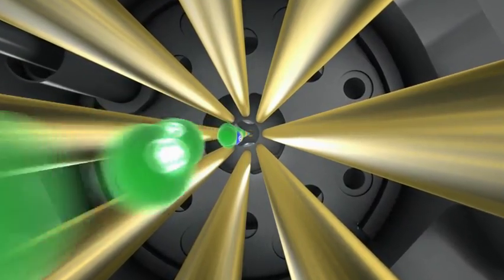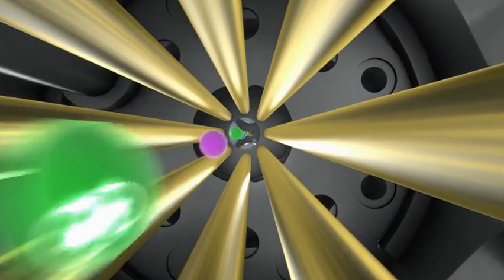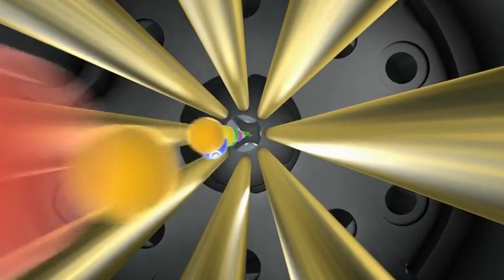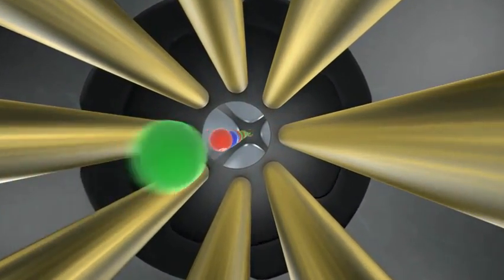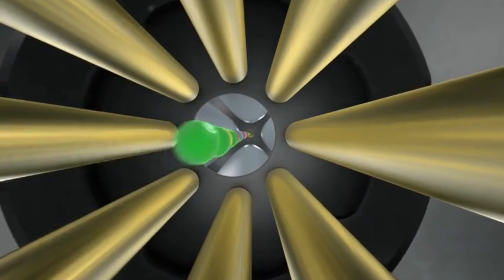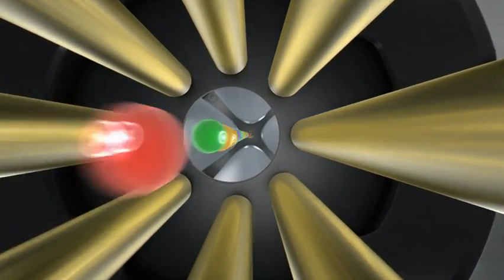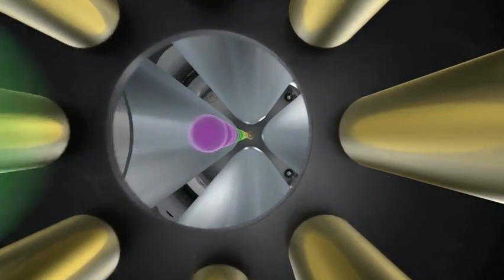Newly engineered ion transfer optics increases precursor ion transmission for higher sensitivity and precision. The new optical lens elements reduce contamination and enhance the ease of auto-tune. This improves overall system robustness.